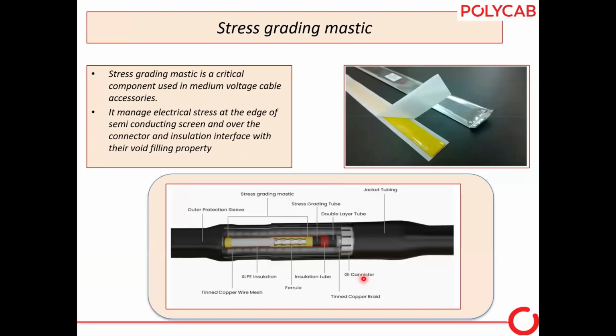Now let's see. This sequence is like that. We have made the joint with that ferrule. Over that, we have to use the stress grading mastic, because after crimping, air gaps form at this point. So you have to fill those air gaps with stress grading mastic. You have to use the stress grading mastic here and at this point also. The stress grading mastic is a very critical component, and we have to use it because whatever steps form at the edge of the semiconducting screen at this point should be avoided. That's why we use the stress grading mastic. It has a good void filling property.